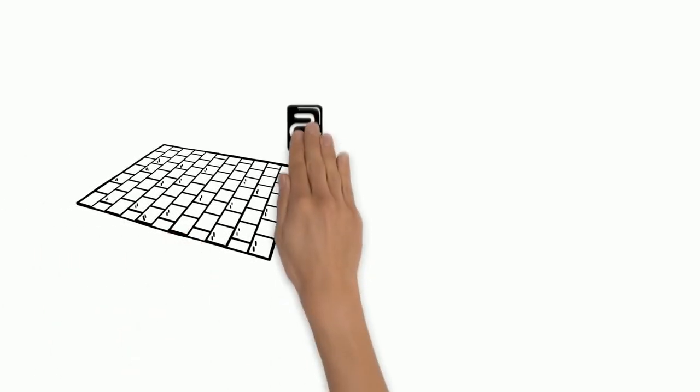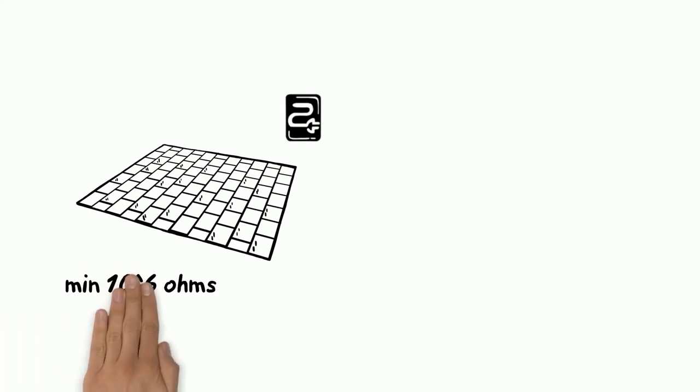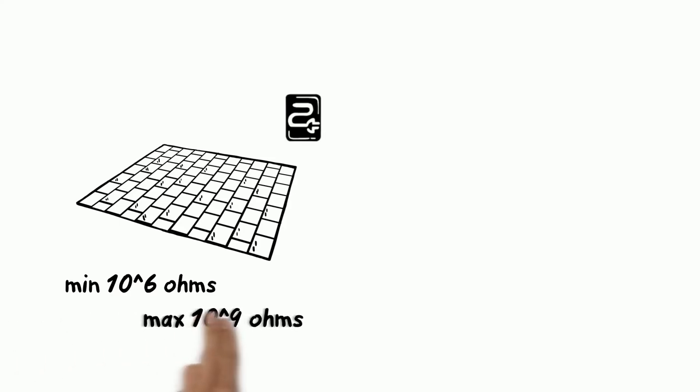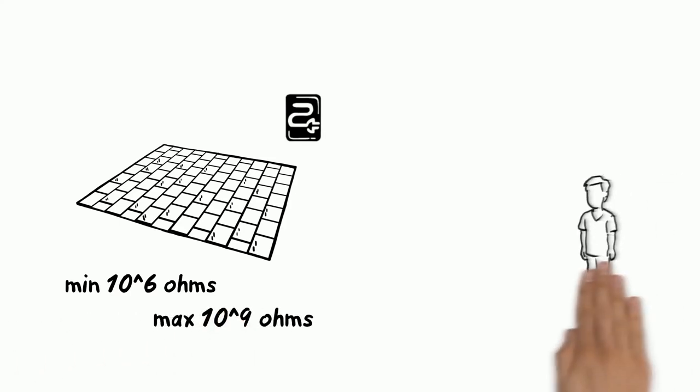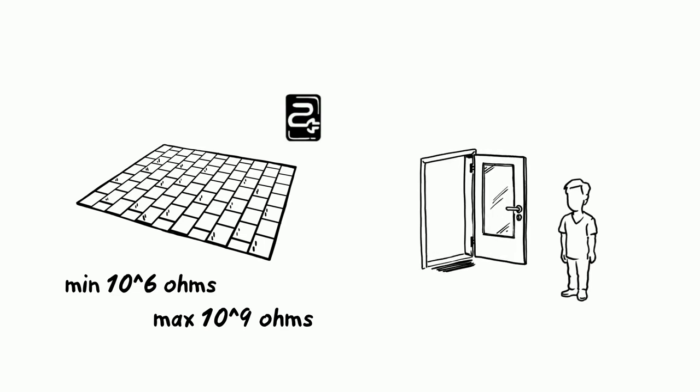Floor coverings have a different electrical conductivity. A conductive floor, for example, has an earth leakage resistance of at least 10 to the power of 6 ohms and a maximum of 10 to the power of 9 ohms. This conductivity ensures that each person discharges when entering the room, and thus there is no longer risk of explosion.